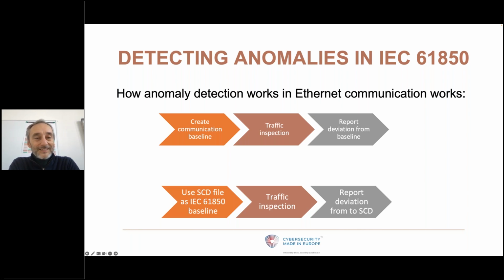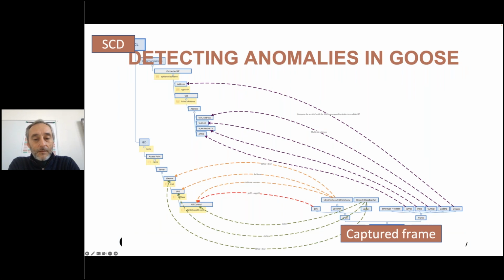We've seen this pretty much already. You've got your SCD file and your captured frame, and you match the different attributes in the packet to the SCD: your MAC address, your VLAN ID, your app ID, your GOOSE control block, GOOSE ID, etc. Then you can report if this is seen on the network but not defined in the SCD.